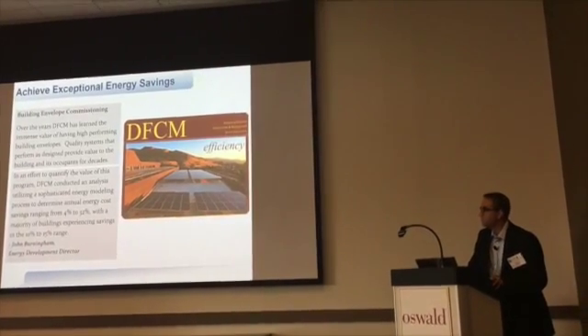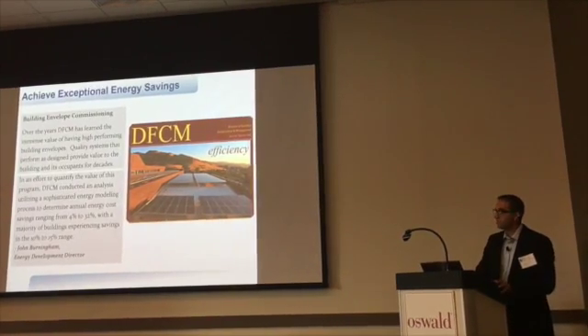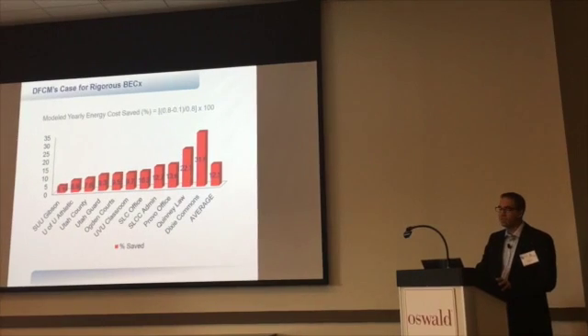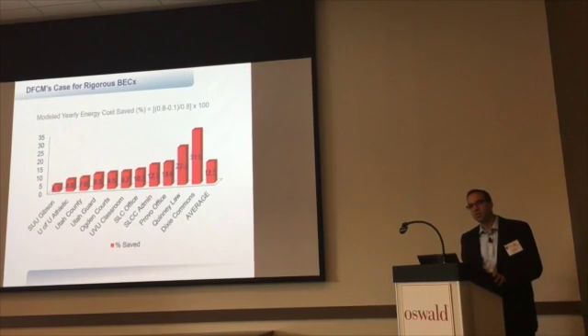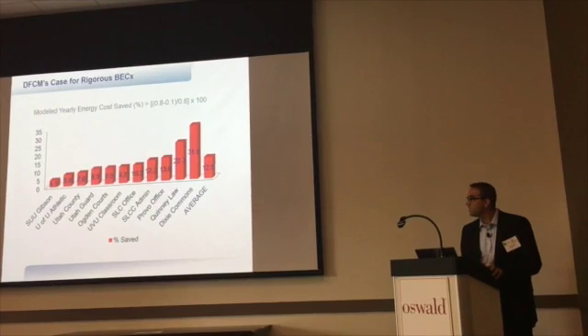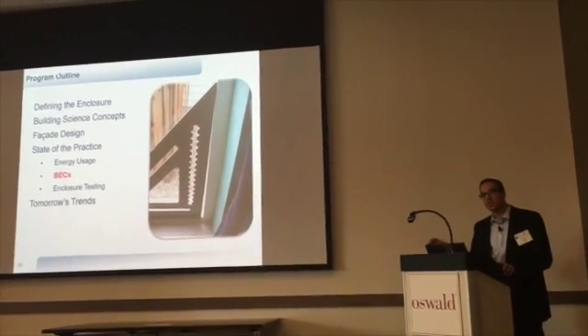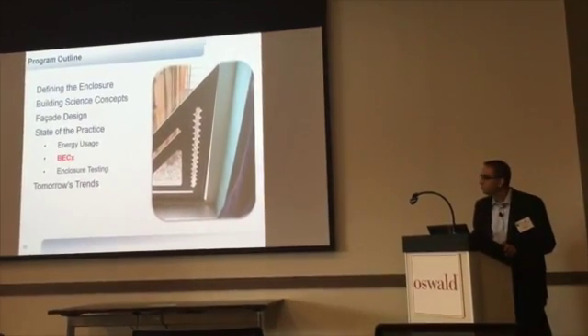The study showed annual savings of 10% to 15% on buildings that had the commissioning exercise versus those that didn't, done over about 30 different buildings. Savings varied based on climate. Interestingly, the biggest savings — 31.9% — was actually in the desert in one of the hottest locations, which you wouldn't expect. You'd think the enclosure would have a greater impact in a cooler environment. It's hard to get this much data in one spot — the state of Utah probably has some unique data in that respect.